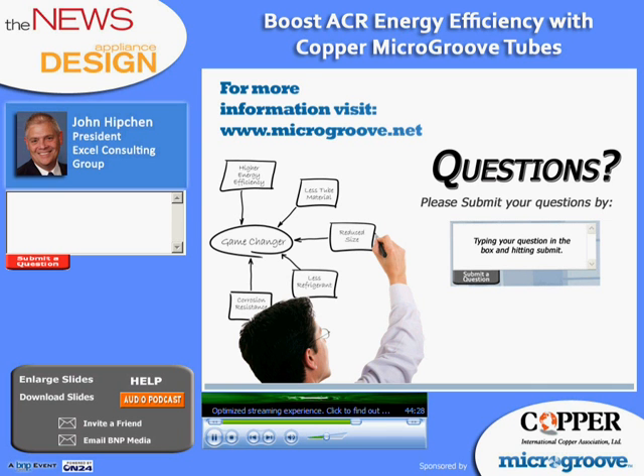Now, you mentioned propane. Has this been used with carbon dioxide, CO2 systems? Copper microgroove tubes are, in fact, being looked at for CO2 designs, and I believe there are OEMs that have generated data on those systems. If somebody is interested in that, I would suggest they get a hold of us separately, and we'll see what kind of data we can dig up. Most of those studies, though, tend to be proprietary at this point. But like I said, we can see what we can dig up that we'd be able to relay to the outside world.